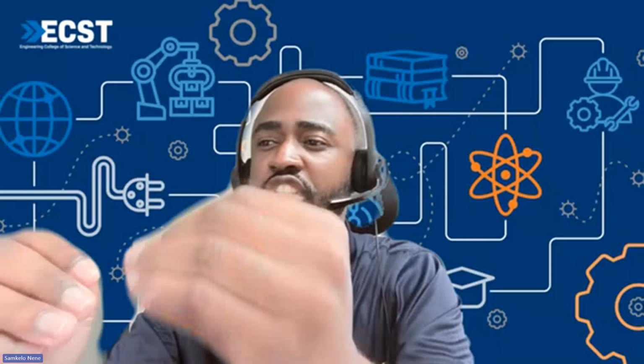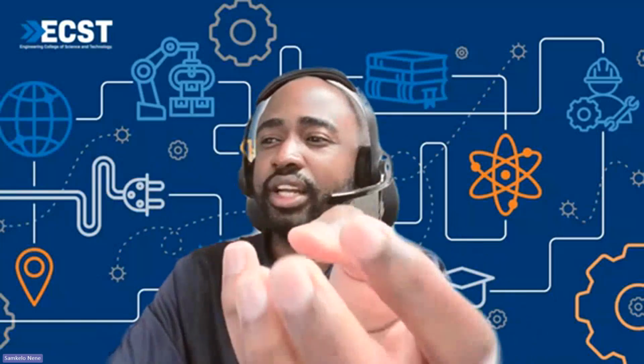You can't say because there's so much generation, it's so good. It's not good for the system. At all times, there has to be a match between the generation and the demand for the system to be stable. Because obviously high generation will lead to higher frequency, and that can lead to mechanical damage on the generator equipment at the generation side of the power system. And also you can't say it's okay, we can work with less load. That will bring the frequency down, and obviously it will burden the grid because there'll be more demand on the grid.